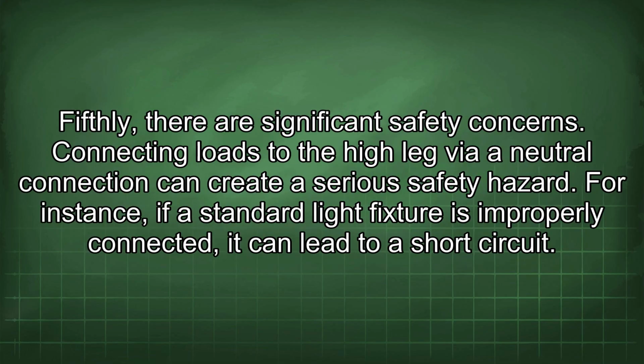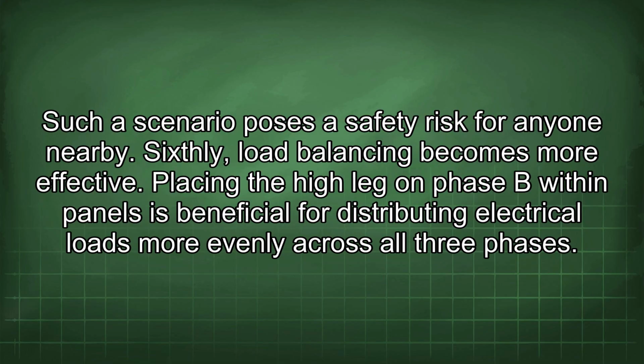Fifthly, there are significant safety concerns. Connecting loads to the high leg via a neutral connection can create a serious safety hazard. For instance, if a standard light fixture is improperly connected, it can lead to a short circuit. Such a scenario poses a safety risk for anyone nearby.